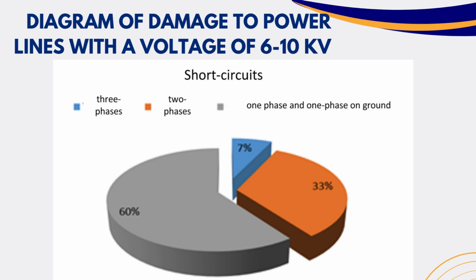On this slide you can see diagrams of damage to power lines with voltage 6 and 10 kV. As you can see, single-phase faults in the grid are the most popular, and the most frequent type of internal overvoltage in 6 to 35 kV networks is overvoltage associated with single-phase earth faults, accounting for up to 80% of all.